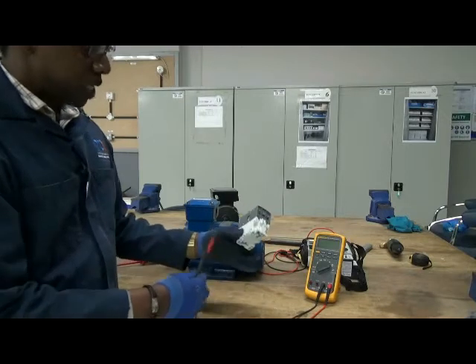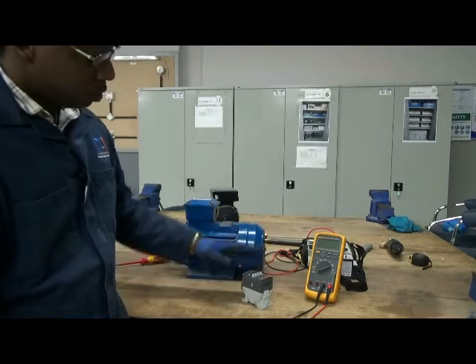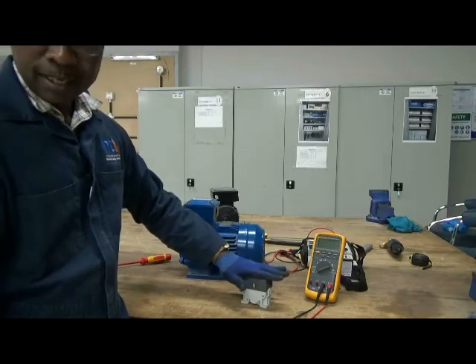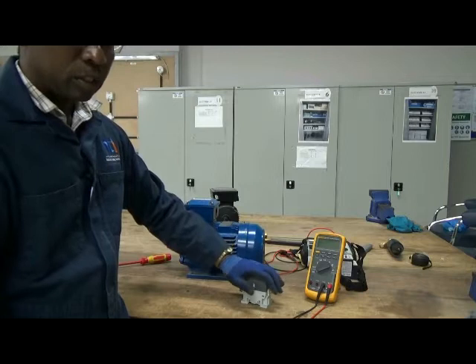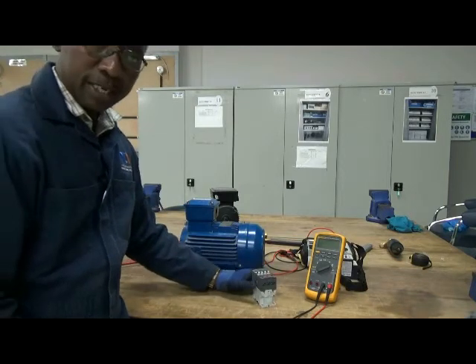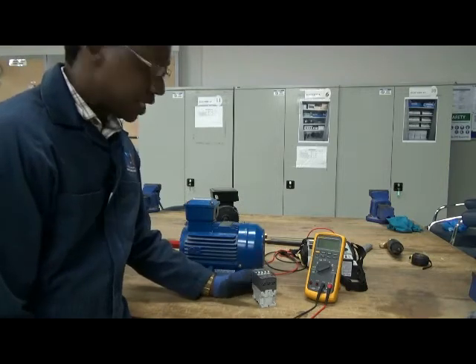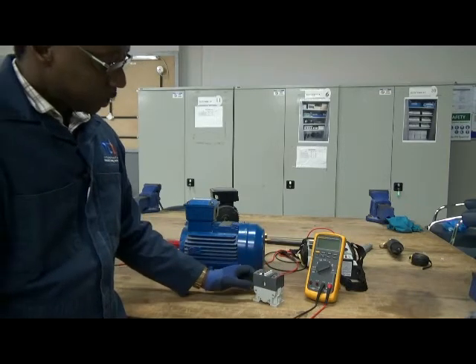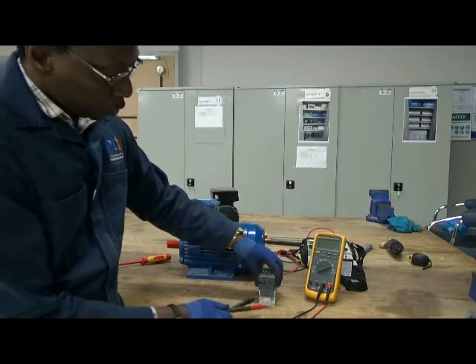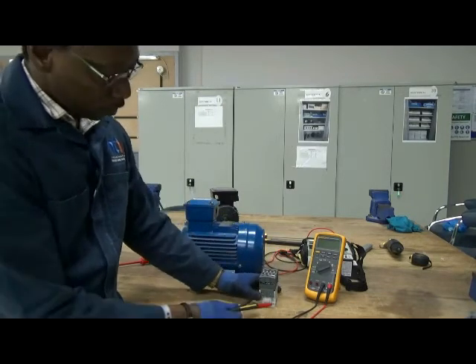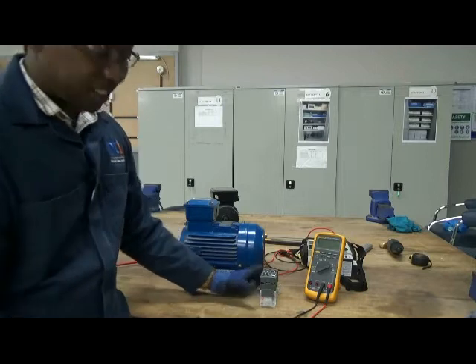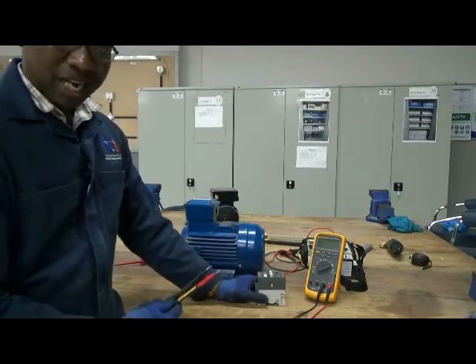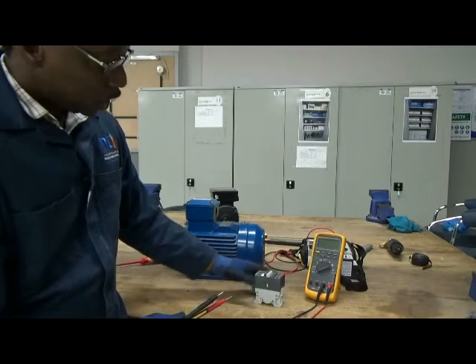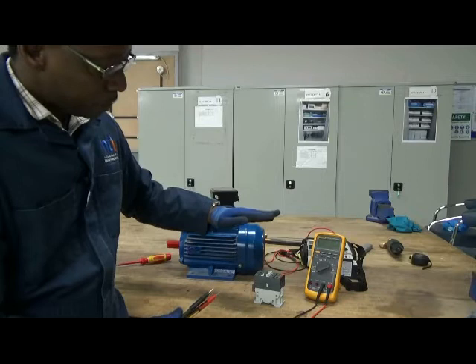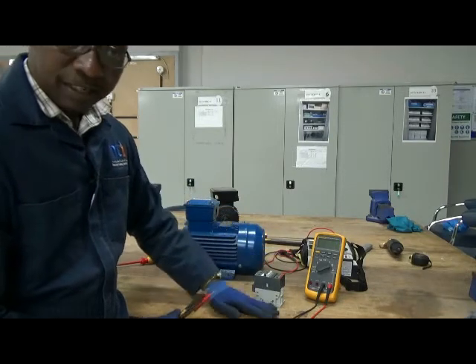It is made up of a coil inside, and it has got what we call main contacts that are open, and it has got some auxiliary contacts that can either be open or normally closed. So what happens as far as operation is concerned is when you supply power or voltage to the coil, which is inside, you connect maybe your live and neutral on those 2 points, the coil gets magnetized. And when it's magnetized, it will pull the set of normally open main contacts and close them.